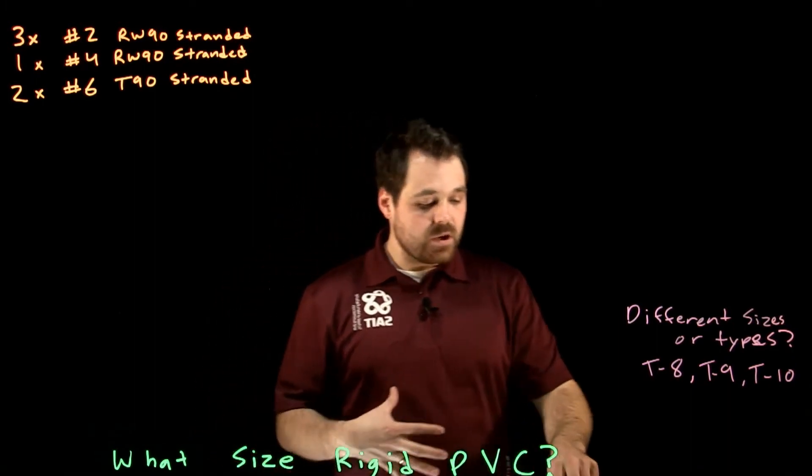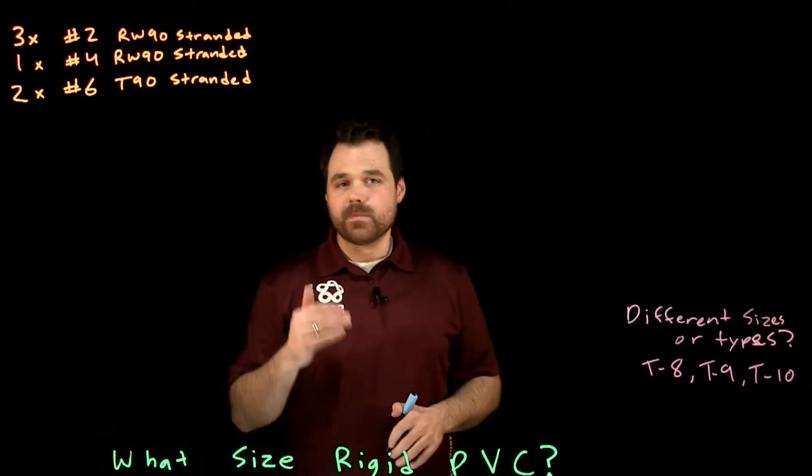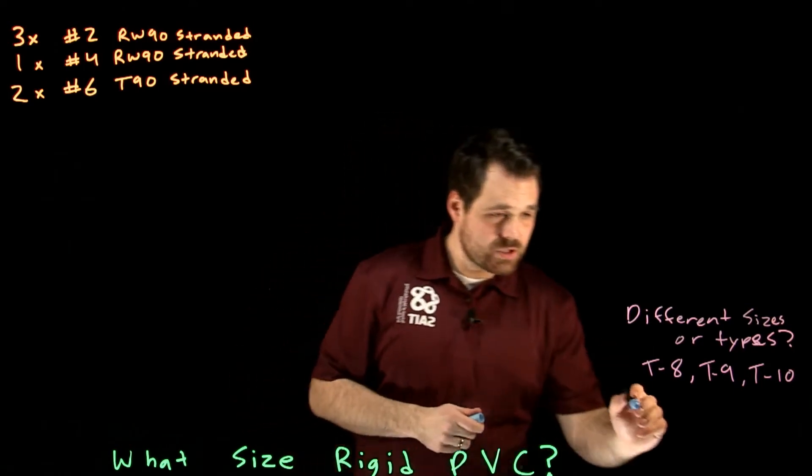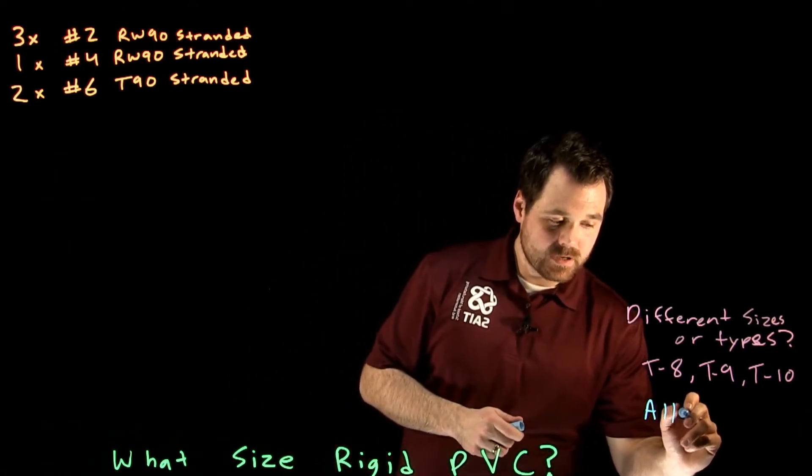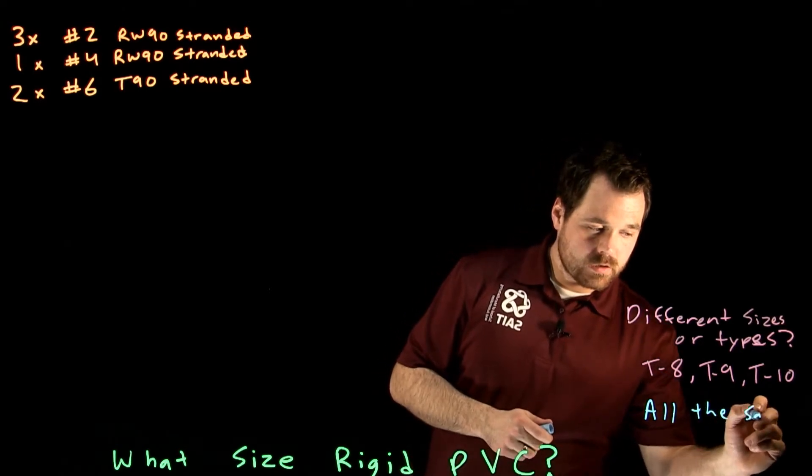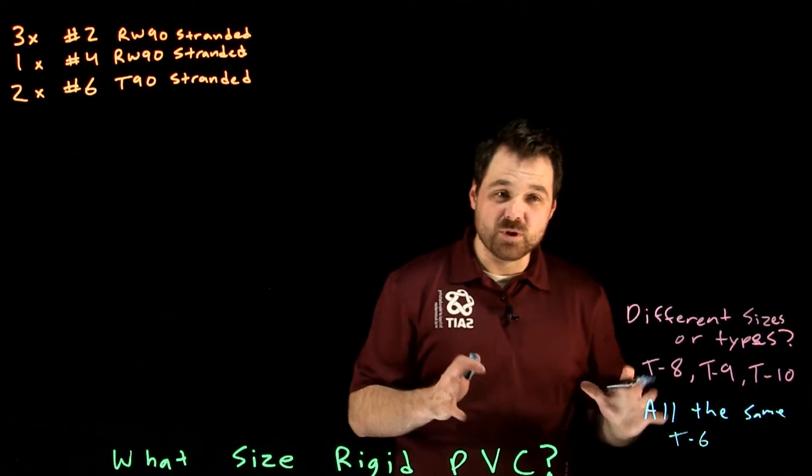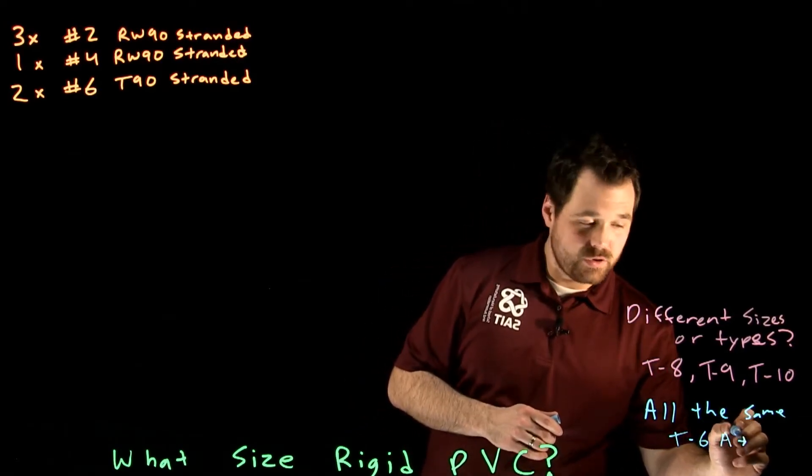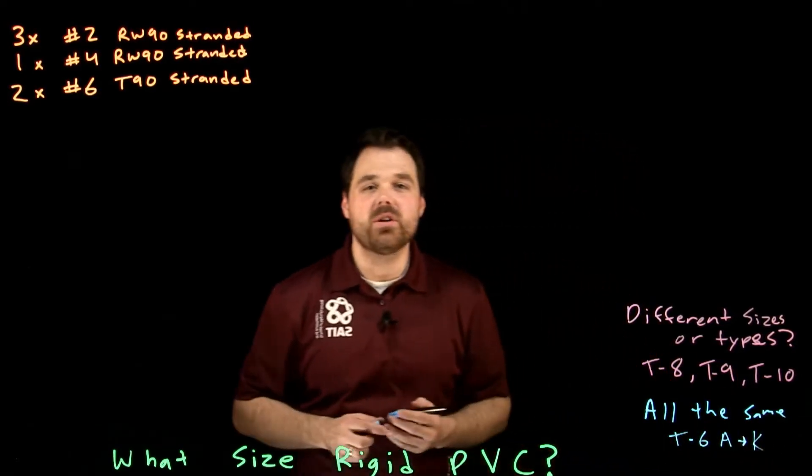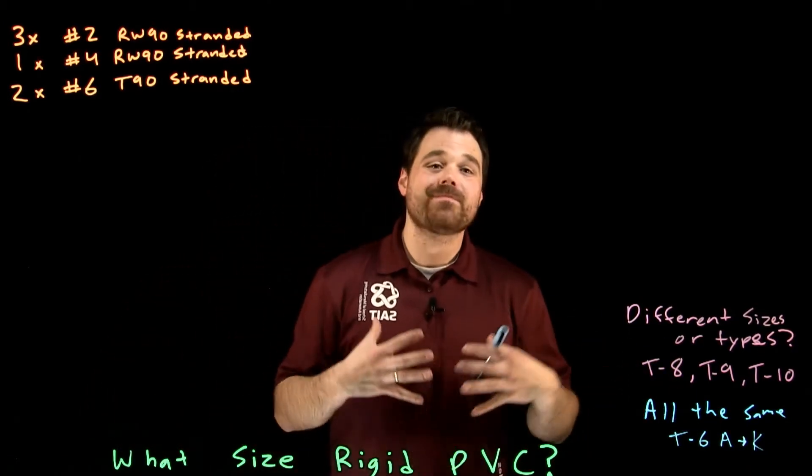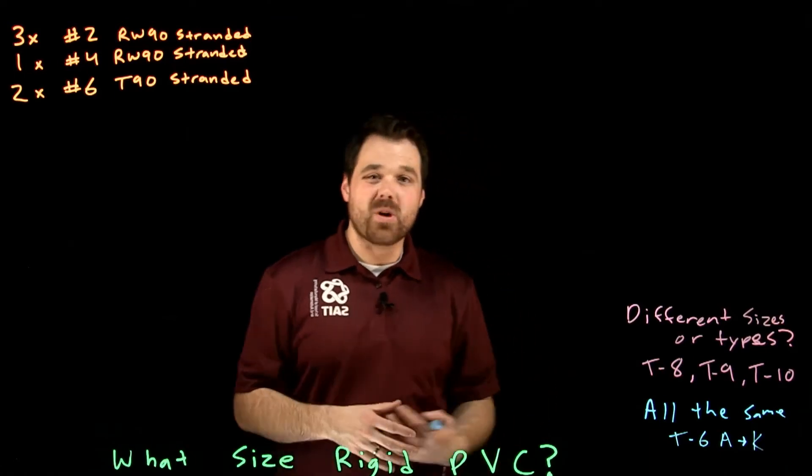However, if you are working and you have all the same types of conductor, like let's say all RW90, all number six, we can actually use table six. And table six actually goes from A all the way through to K based on the different conduit type. A little bit quicker, table six, but eight, nine, ten is going to be a lot more accurate.